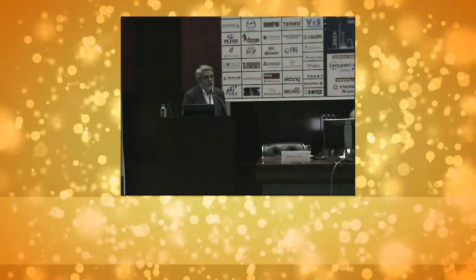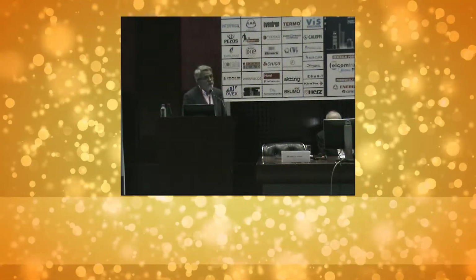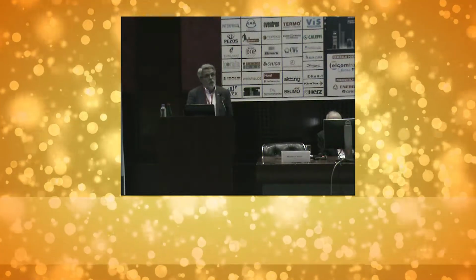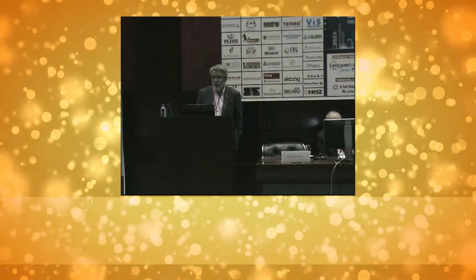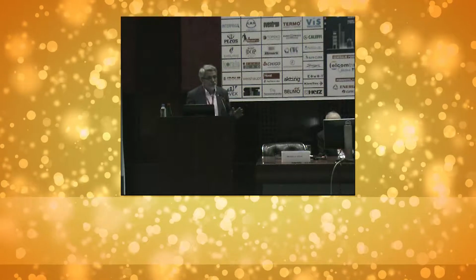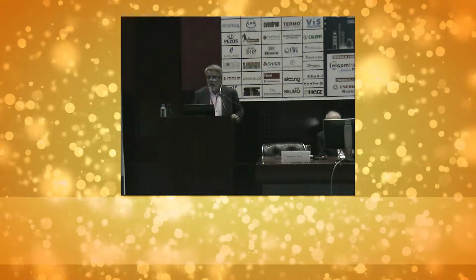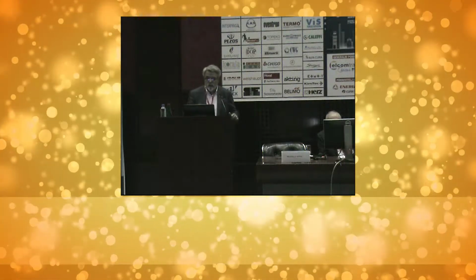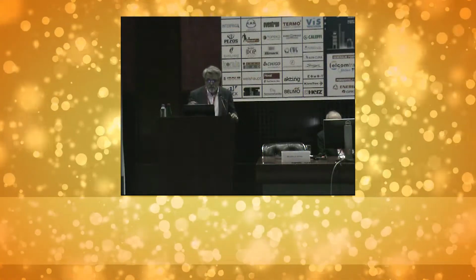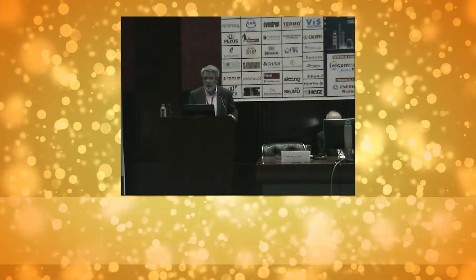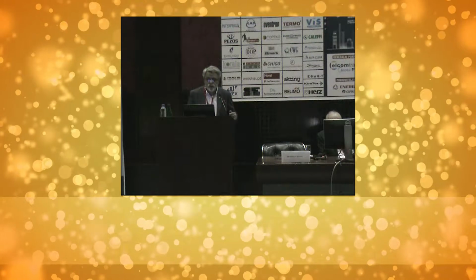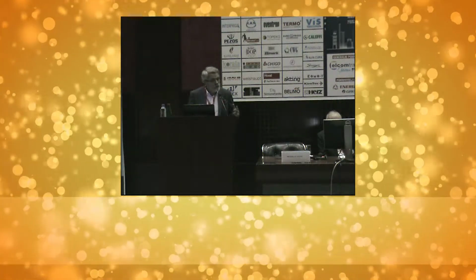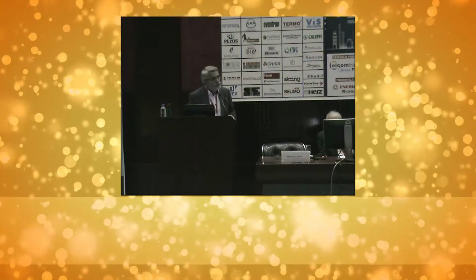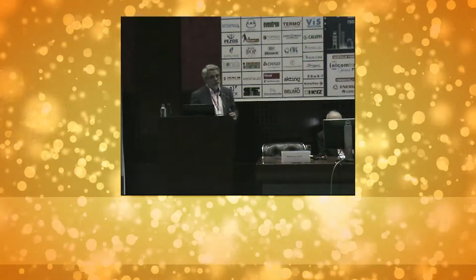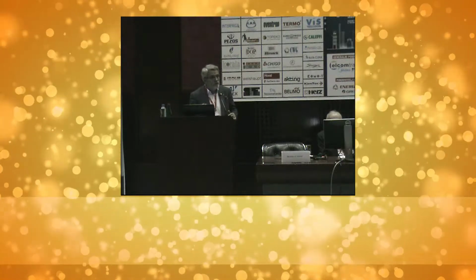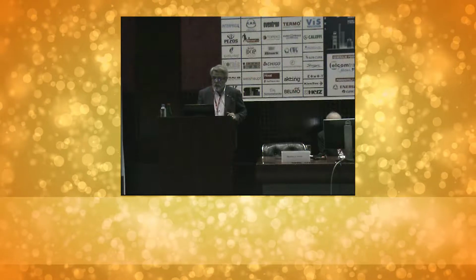That's why I tried to change the design of this ice rink a little bit, and I chose to make indirect vaporization, also using ammonia. I chose ammonia again, taking into account a lot of refrigerants. In these slides there are only 4 of them. If you take into account all the data here, which we calculated using the theoretical cycle, you can see that we can choose 2 refrigerants, ammonia and CO2. But in the last slides I will come back to show you an analysis of the risk of using CO2 for an ice rink, which led us to choose ammonia.